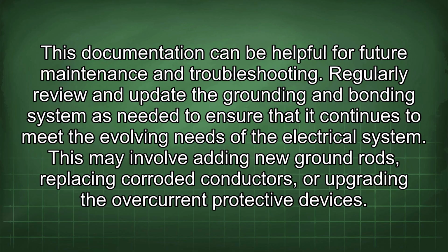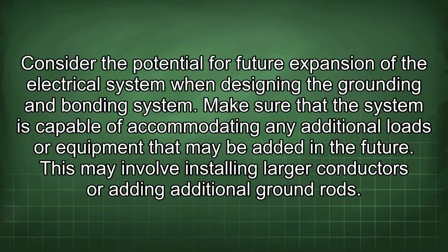Regularly review and update the grounding and bonding system as needed to ensure that it continues to meet the evolving needs of the electrical system. This may involve adding new ground rods, replacing corroded conductors, or upgrading the overcurrent protective devices. Consider the potential for future expansion of the electrical system when designing the grounding and bonding system. Make sure that the system is capable of accommodating any additional loads or equipment that may be added in the future. This may involve installing larger conductors or adding additional ground rods.